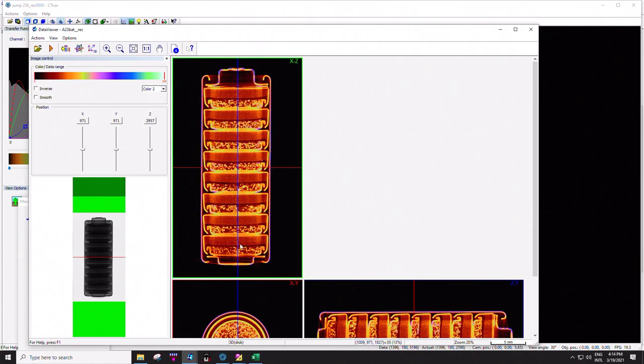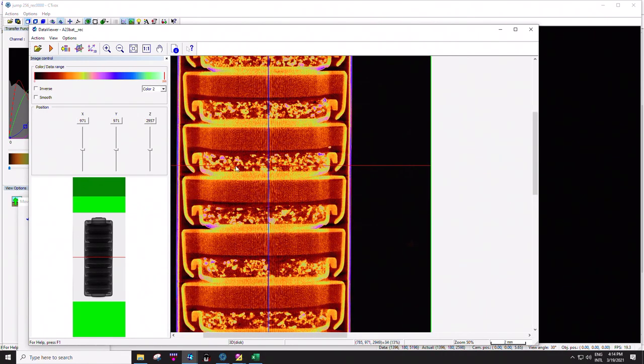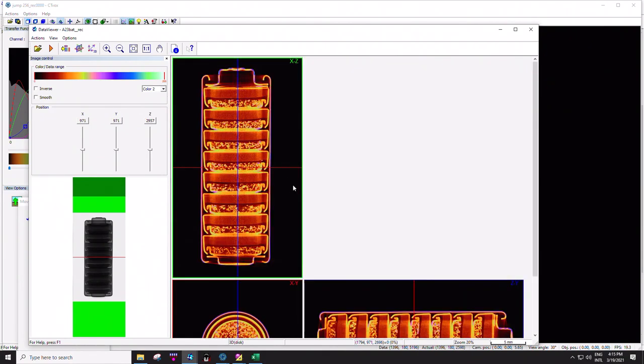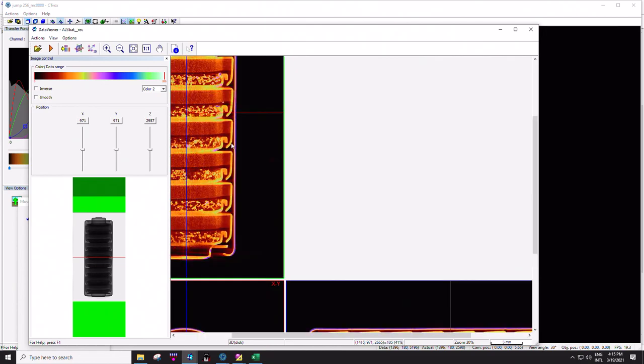The last sample I brought in was a battery. Most of these batteries are just a can — maybe they have some wraps inside of the different anode and cathode materials. Right, but this is surprising. Here is your battery. Oh wow — it's not one battery. It's actually a stack of eight button batteries all together. So that's how they get that high voltage out of this little battery — I'm assuming this is a 12 volt battery. But you can see each individual battery; you could make out the details, these seals right here. You can see the anodes, the cathodes, and all the packing material on the inside. So we would actually be able to tell if we had a problem with the lowest cell versus the top cell as we cycle these things. Absolutely, and if there was some sort of problem on the inside, we could definitely see that as well.